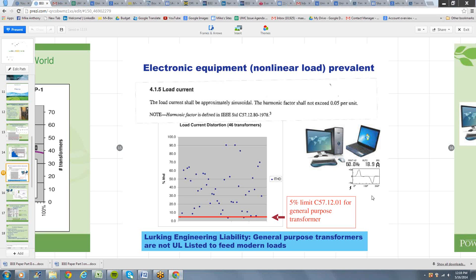And that's important from a couple of perspectives. First of all, if you have a general purpose transformer, or if you were thinking about specifying one, you've got a UL listing problem, because those transformers are designed per the UL spec to 5% THD being the limit of what its UL listing is for. As you can see by the scatter plot of current THD from a sample of transformers, almost all of them are above that, not just a little bit above that red line limit, but far above it.